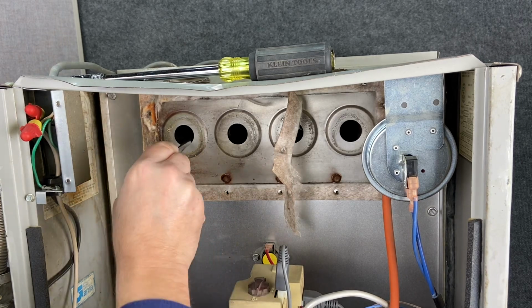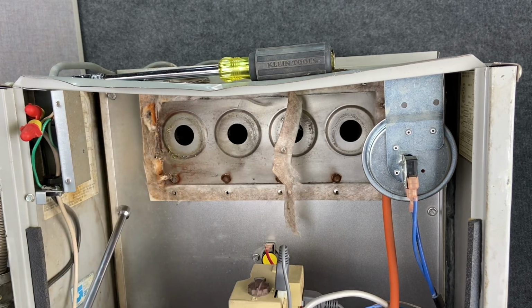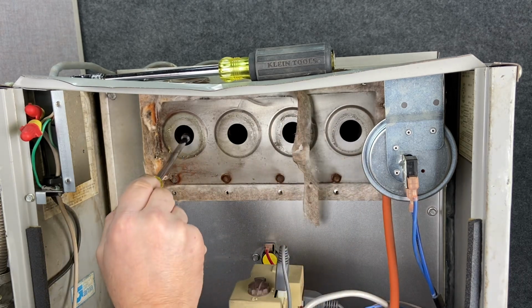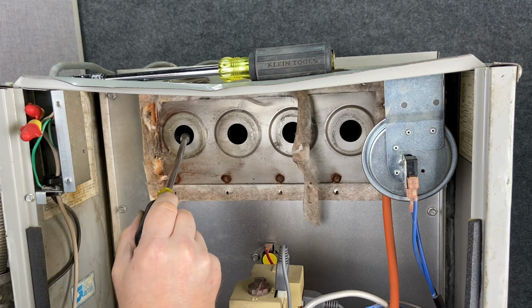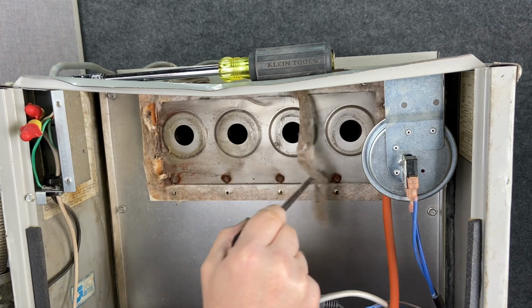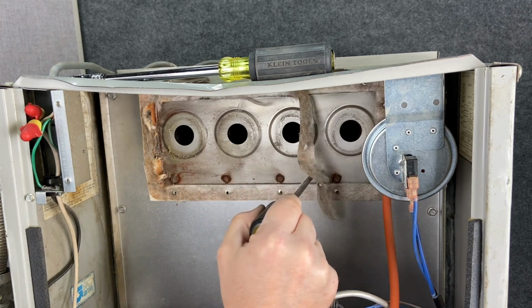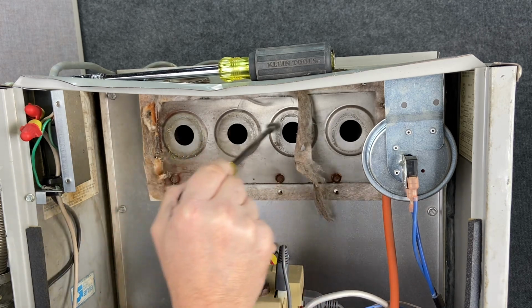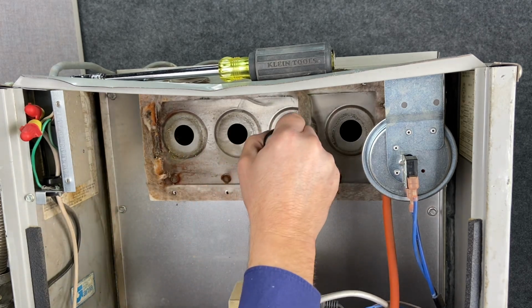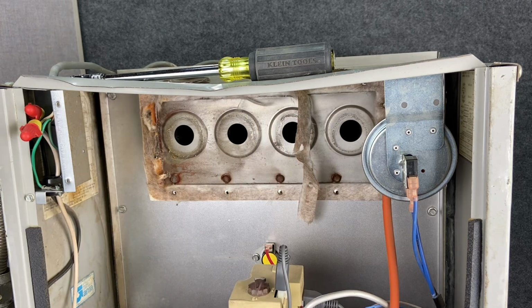So this furnace, this heat exchanger side here, I wouldn't be surprised if there's not a hole in it. This side looks in really good shape. As we pull this heat exchanger out, we'll get a better look. These screws here actually hold the heat exchanger to this panel, but this is the individual heat exchangers. Any air from inside of here is separate from the air in the house.